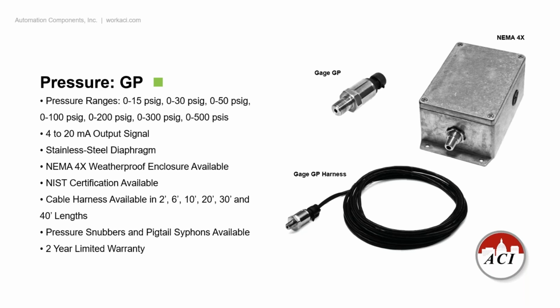It's a Packard type fitting, so you have a depluggable wire harness that goes onto these, and if you want a NEMA 4 enclosure, you can actually put this sensor inside of that, as shown here in the top right. Different wire harnesses, 2 foot is kind of the standard. We can go up to 40 foot in length if needed. We do have all the snubbers and pigtail siphons available as well for those different applications needing that.